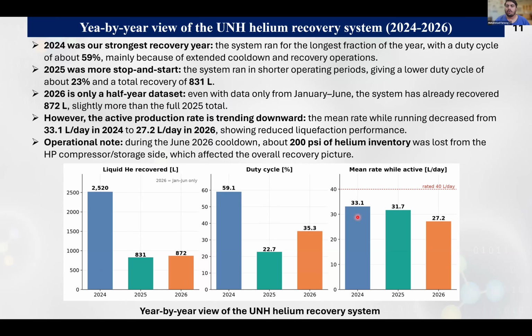In 2024 we were producing 33 liters per day, which was reduced to 31, and now it's reduced to 27.2 liquid liters per day. I'll explain the reason for this degradation from 33 to 27 in the following slides.